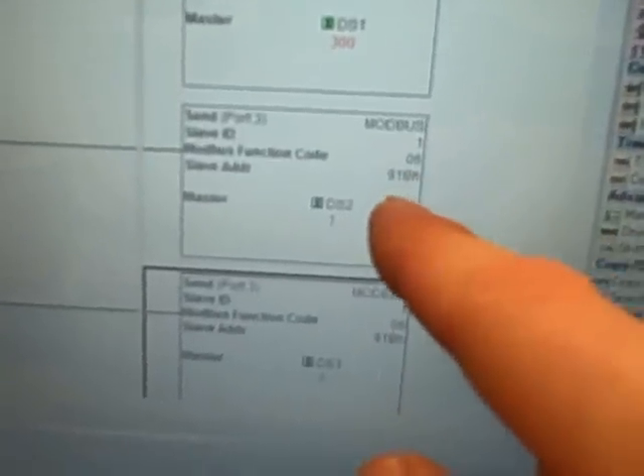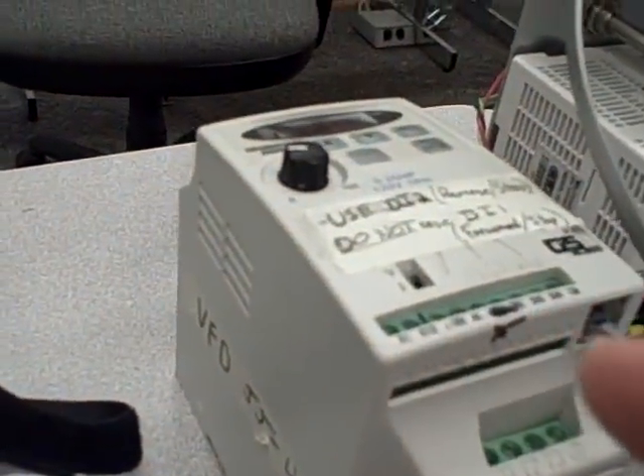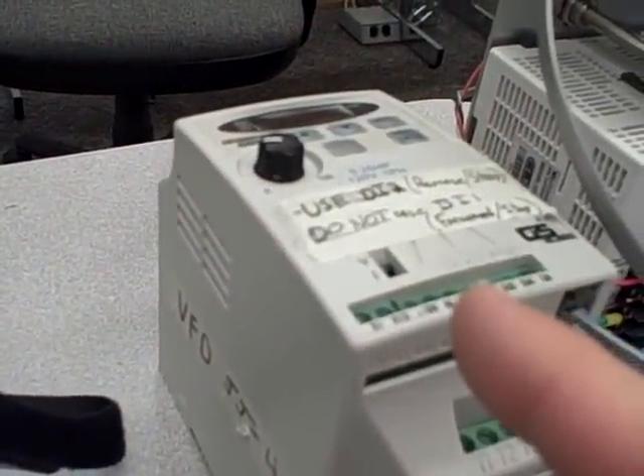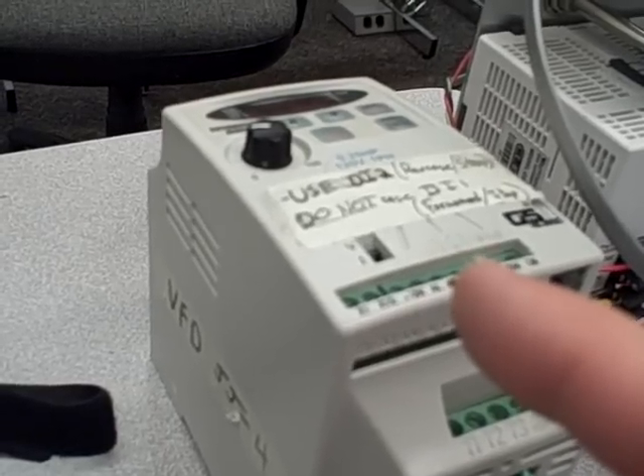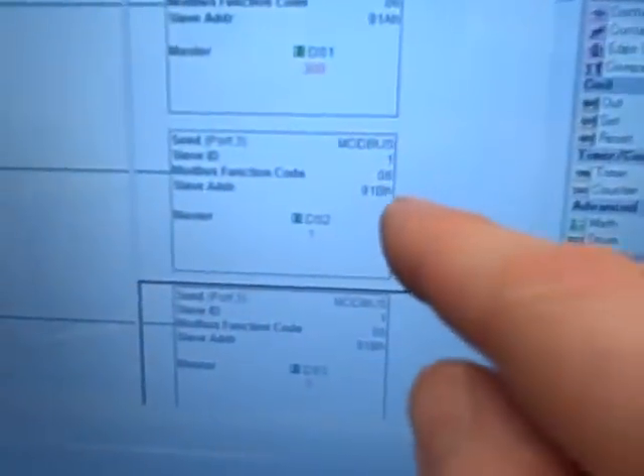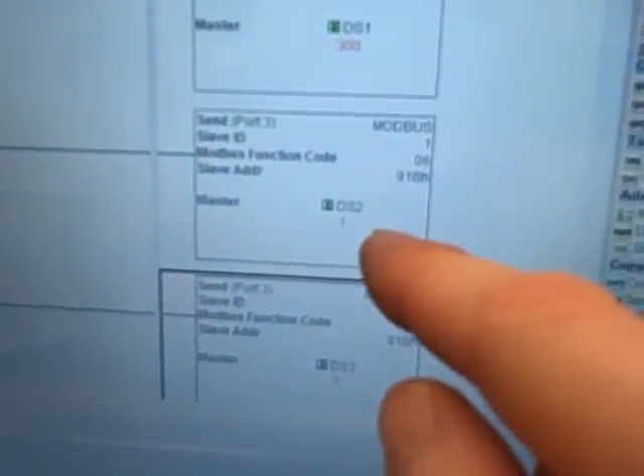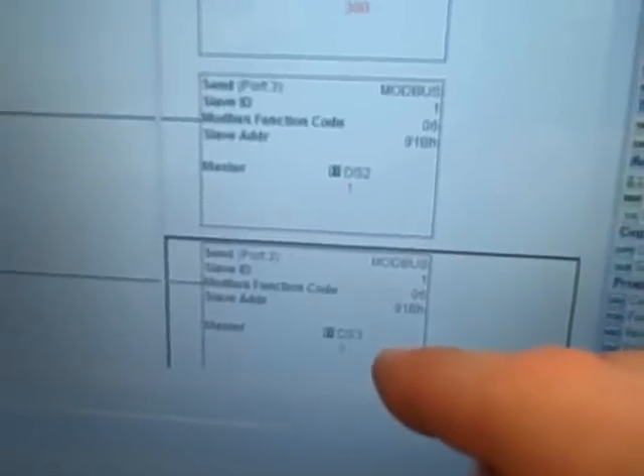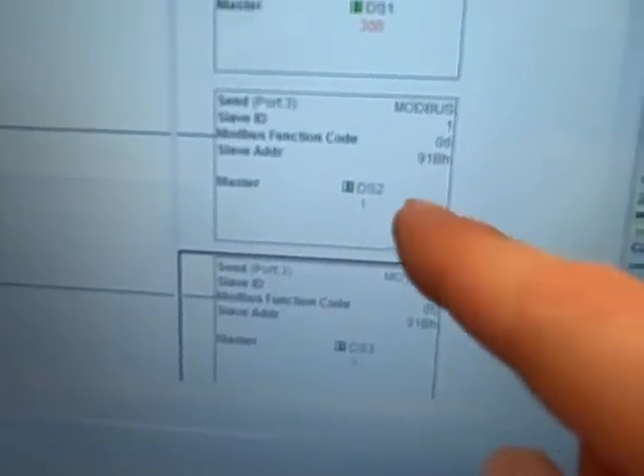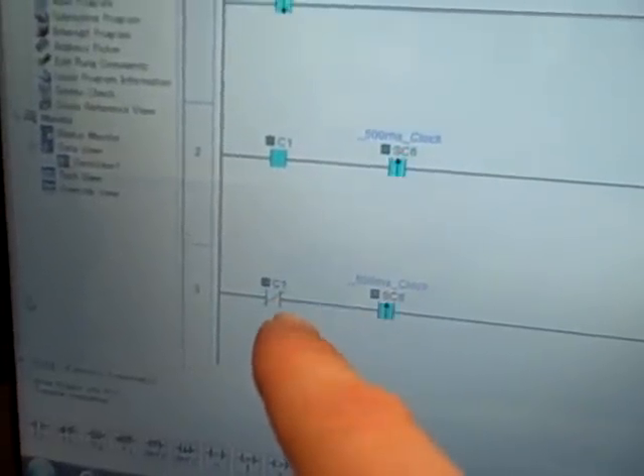For the start and stop command, this is hex address 0x91B. In this Automation Direct drive, instead of writing a single bit to that address to turn it on and off, we have to write a complete 16-bit word to address 0x91B. If the value of that word is 1, it starts; if the value is 0, it stops. We have two pre-programmed integer values, DS2 and DS3 — DS2 programmed to a value of 1, DS3 programmed to a value of 0. We are sending one or the other based on the upstroke of the 500-millisecond clock and the Boolean value of C1, which is our start-stop bit.